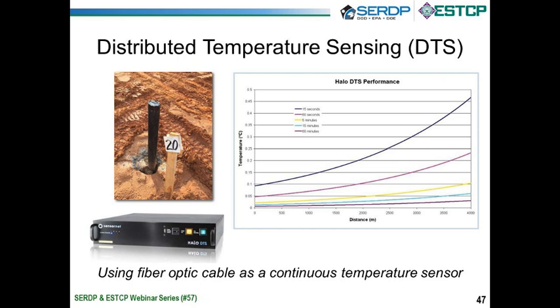We had roughly 2,600 meters of fiber in the ground, which allowed us to get 1,300 independent temperature points with an accuracy to a few hundredths of a degree centigrade. We didn't need more than a tenth, but this is one of the lower end systems, and yet it was all we needed. So I'm really fascinated by this technology.